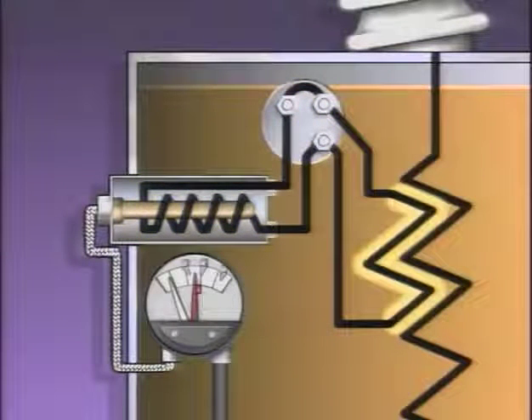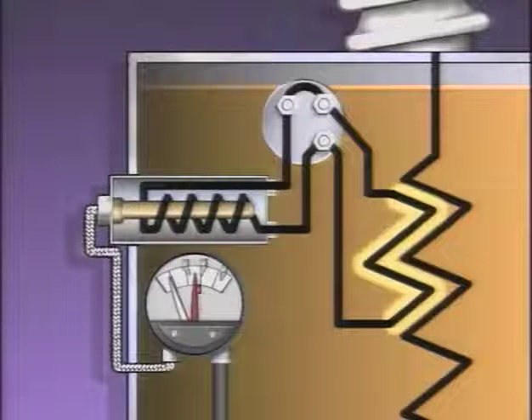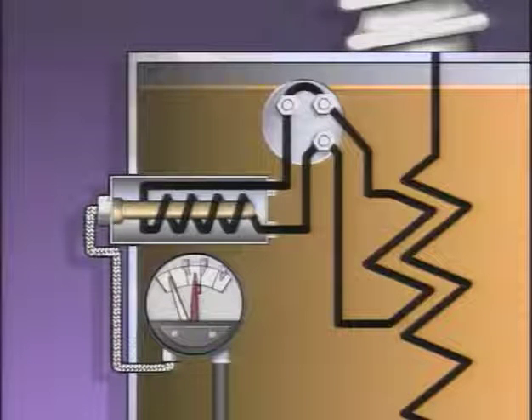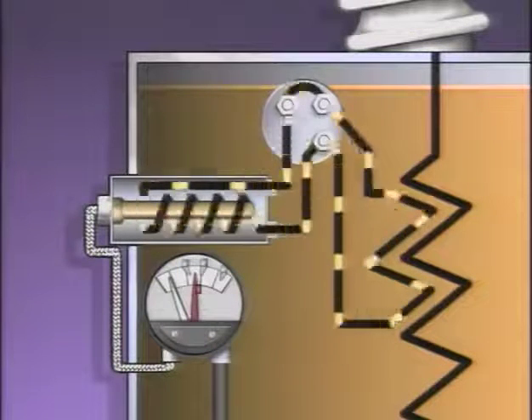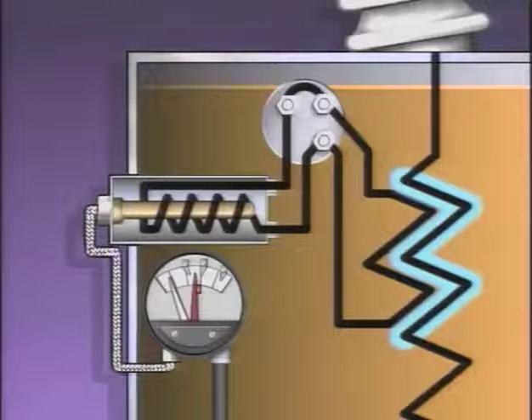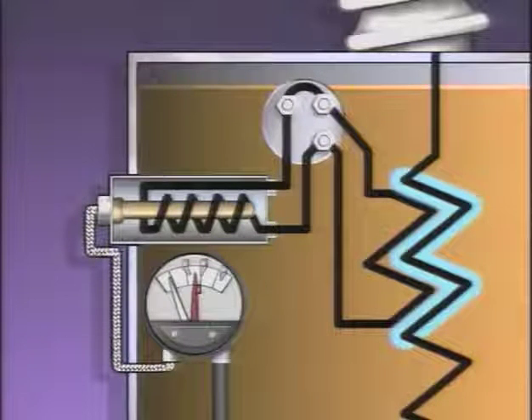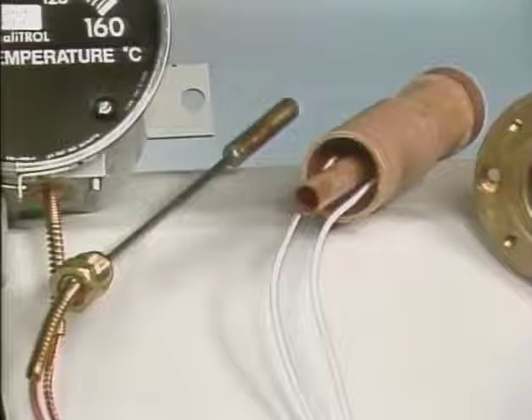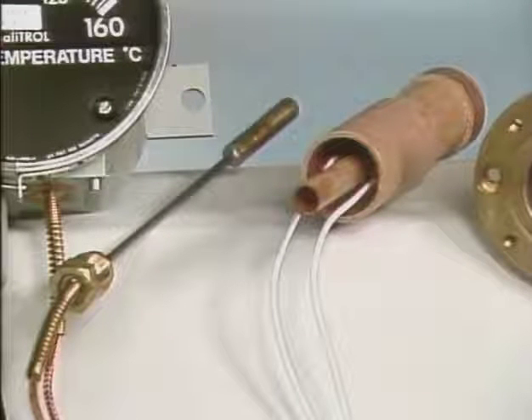The current transformer provides a current that's proportional to, but much lower than, the load current of the power transformer. The function of the current transformer and the heating element is to simulate the temperature rise created by the power transformer winding. The winding temperature is determined by the load on the winding, the thermal characteristics of the winding, and the temperature of the transformer oil. So the heat created by the heating element and the heat of the transformer oil both act on the temperature sensitive bulb.